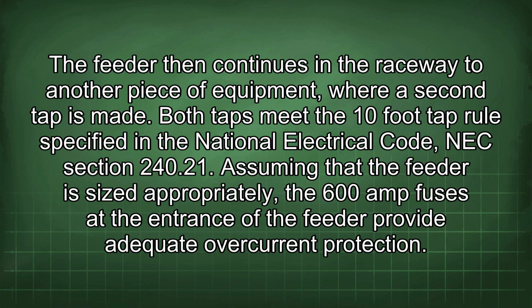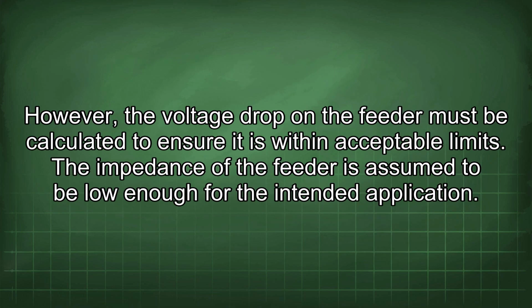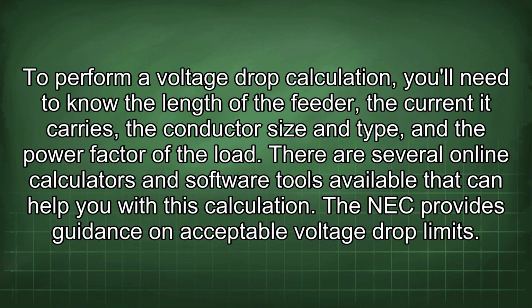Assuming that the feeder is sized appropriately, the 600 amp fuses at the entrance of the feeder provide adequate overcurrent protection. However, the voltage drop on the feeder must be calculated to ensure it is within acceptable limits. The impedance of the feeder is assumed to be low enough for the intended application. To perform a voltage drop calculation, you will need to know the length of the feeder, the current it carries, the conductor size and type, and the power factor of the load. There are several online calculators and software tools available that can help you with this calculation.